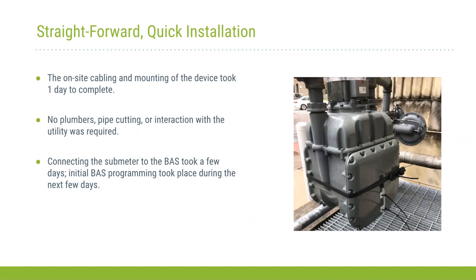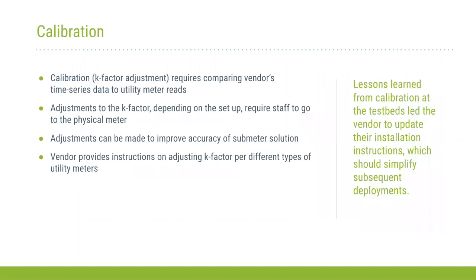Next slide, please. Now, I did touch on this a little bit. The calibration calls for adjusting something called the K factor. The K factor is basically a multiplier when you're installing a submeter. This requires comparing the time series data to the utility meter reads. And if something seems off, you adjust that K factor and then reevaluate the results to narrow in the accuracy of the meter. As I said, we did this during low gas flow, so we didn't have a lot of data to work with. And so it took a little more time than expected to adjust that K factor.